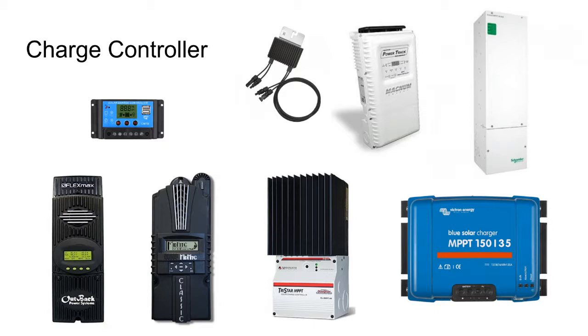Why are all these charge controllers 150 volts? Well, the charge controllers came around before module level panel electronics. And if you're living off grid, you're particularly concerned about shade. One way to mitigate shade is to have smaller circuits and wire them in parallel to each other. So charge controllers came out from an era when the modules were more expensive — maybe you're camping in the woods, got a lot of tall trees around, a lot of shade. You say, okay, we're going to end up doing smaller circuits. For a ground mount, where the wires are all accessible for maintenance and repair, dealing with dozens of circuits isn't fun for install, but it's not the end of the world.